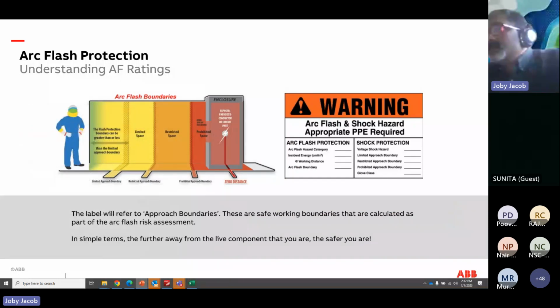And nowadays it's not so complicated. People can do arc flash, not a study, but at least an arc flash risk assessment can be done internally. So if you are only thinking about what level of incident energy is coming out and what level of PPE we need to wear, we can do it through an arc flash risk assessment. If you want to mitigate the arc flash incident energy, then you need to do a detailed arc flash study, and we have to find an arc flash mitigation solution. And there are several ways we can mitigate the arc flash, as various engineering controls can be put in place, not only the calculative way.